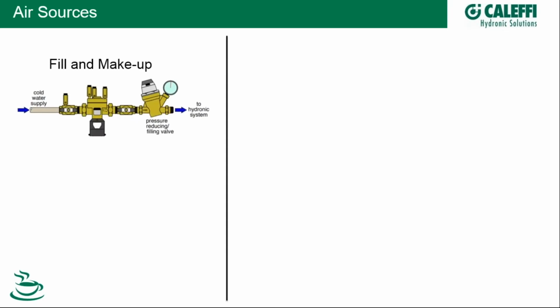Okay, why are we worried about air? Well, what are the sources of air in a hydronic system? Well, firstly, the initial fill of the system and any makeup, that mains water supply has air in solution, and the air in solution is waiting to come out of solution as soon as it is heated up or undergoes a sufficiently large pressure drop in your hydronic system. And that's what we want to take advantage of when we eliminate air out of a system, that property of air coming out of solution. So first and foremost, the biggest source of air is the initial fill, and then also makeup.